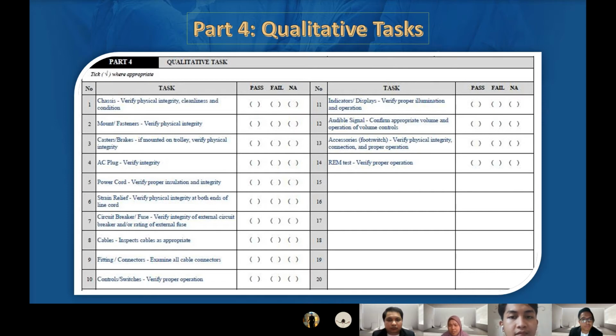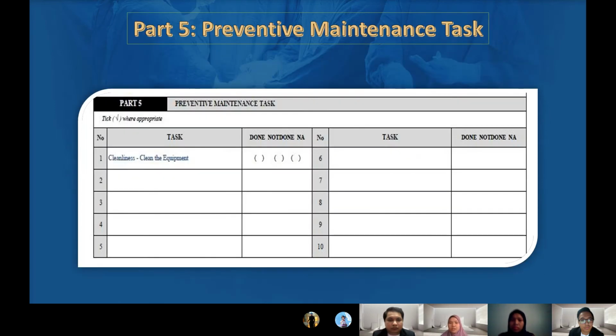For the REM test, the return electrode, check the indicator. If it's green, it means it's applied properly; if it shows red, there's something wrong with the application of the return electrode. That's all for me, thank you.